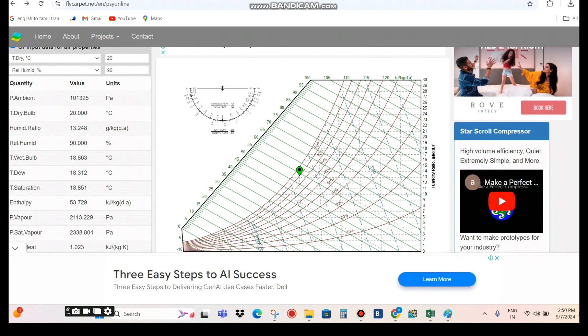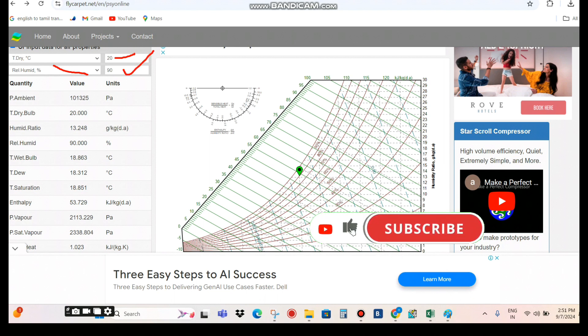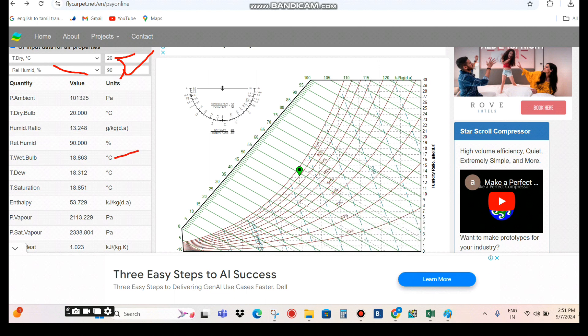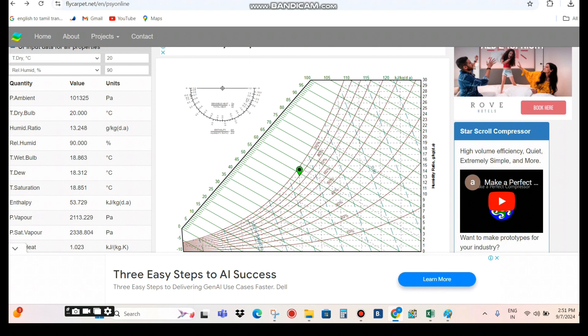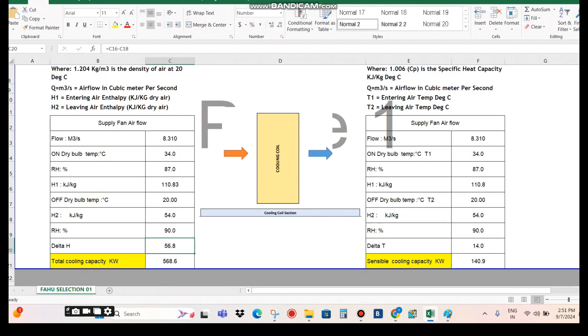After the cooling coil, the relative humidity will always be very high — typically 85 to 90%. I consider 90% RH for the off-coil condition. With off-coil dry bulb of 20°C and 90% RH, the resulting wet bulb temperature is 18.863°C and the enthalpy is 53.729 kJ/kg. I round the enthalpy to 54 kJ/kg for the calculation.